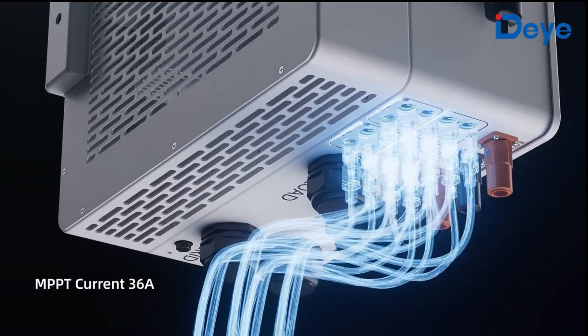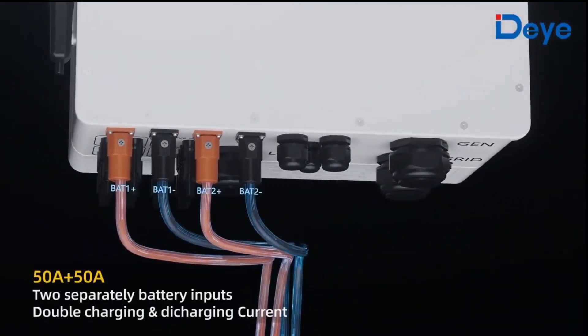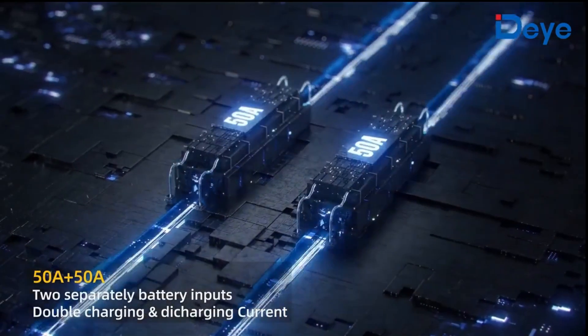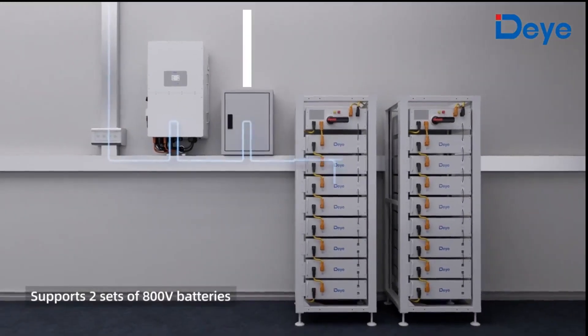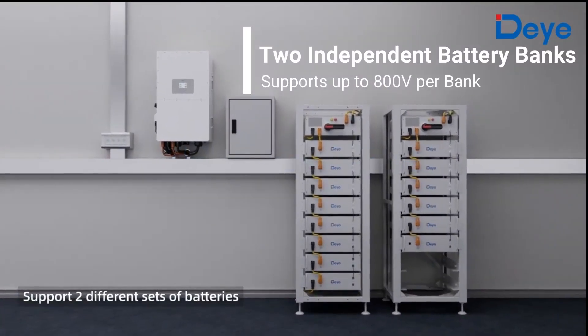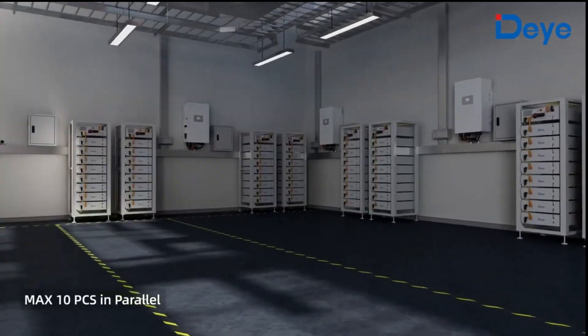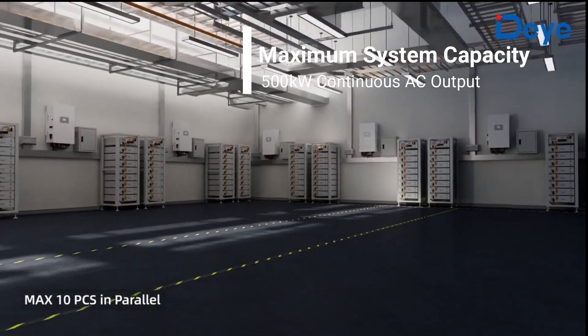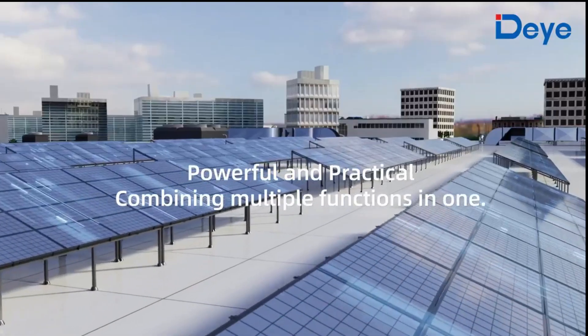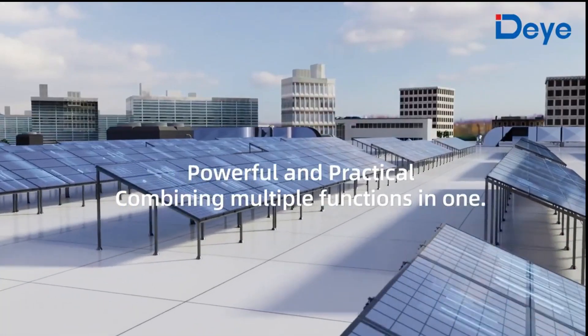With its groundbreaking double charge double discharge function, the new 50 kilowatt three-phase hybrid inverter from Deye supports two independent 50 amp high voltage battery banks of up to 800 volts each. It also supports up to 10 units in parallel, allowing a maximum system capacity of 500 kilowatts.